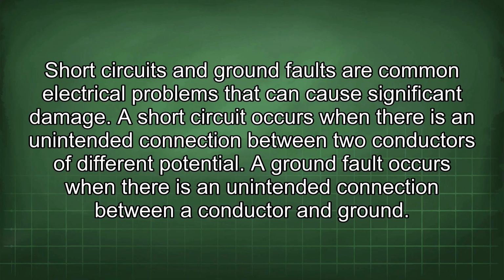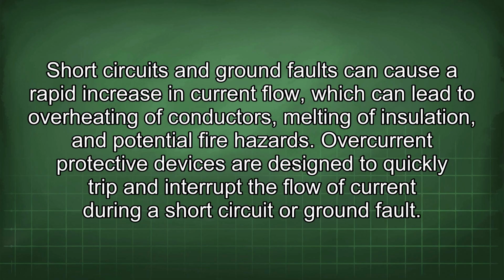Short circuits and ground faults are common electrical problems that can cause significant damage. A short circuit occurs when there is an unintended connection between two conductors of different potential. A ground fault occurs when there is an unintended connection between a conductor and ground. Short circuits and ground faults can cause a rapid increase in current flow, which can lead to overheating of conductors, melting of insulation, and potential fire hazards.